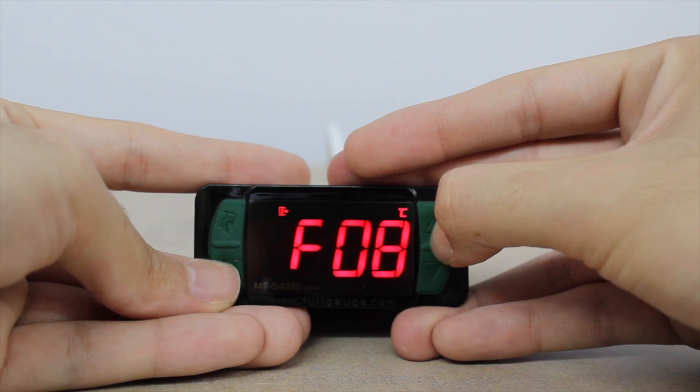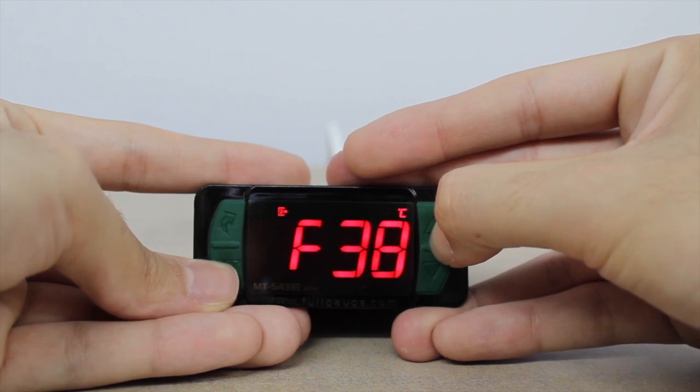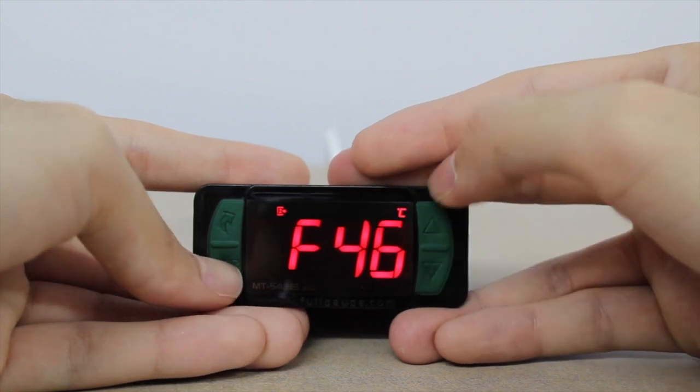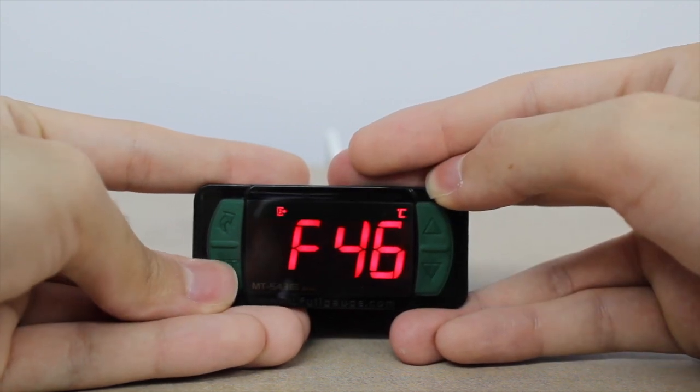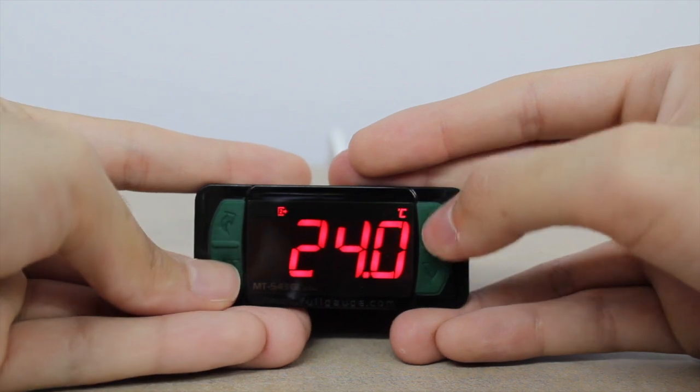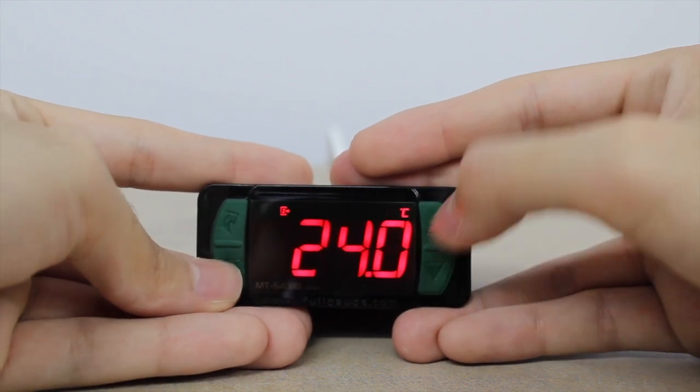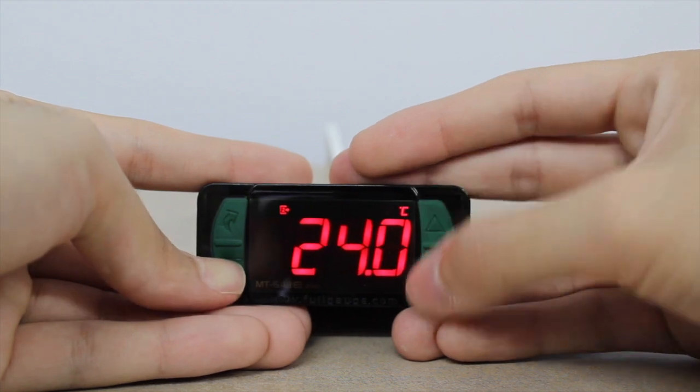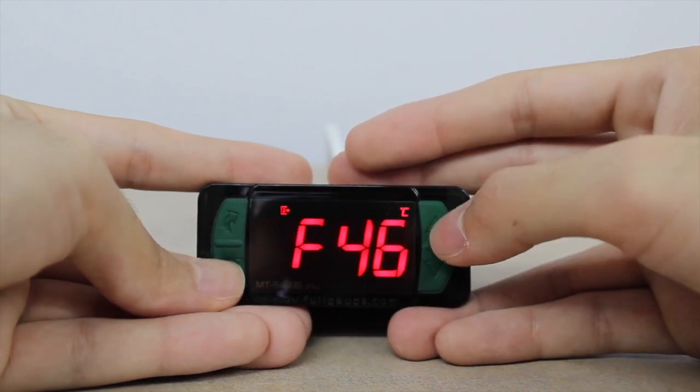Then let's go to Function F46 to set the first level temperature, defined here as 24C. We'll set the time in minutes of this first level in F47, defined here as 10 minutes.